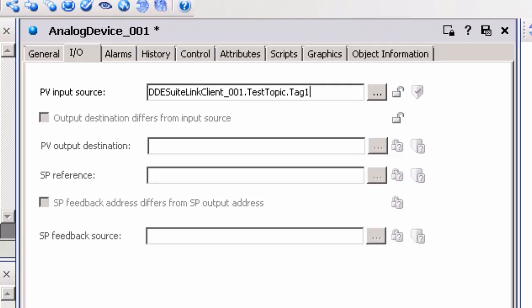If using a device address, the format should be device address at data type, where the at data type is an optional appendage. If not specified, the default data type for the device address will be used. For our example, we will use TestTopic.tag1. If we were using a dynamic address, we would enter TestTopic.R0001@Word, where R0001 designates the address in the PLC and AtWord specifies the desired data type.